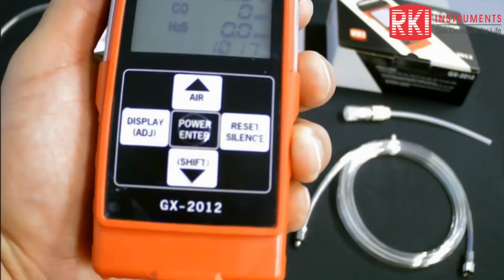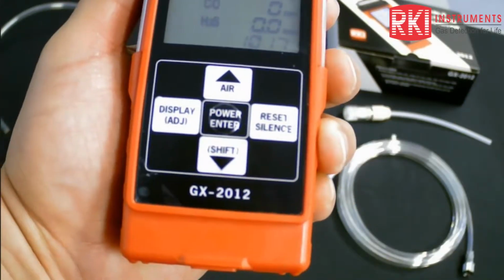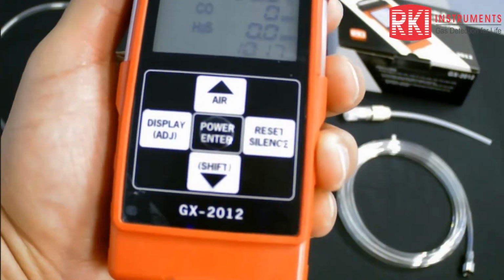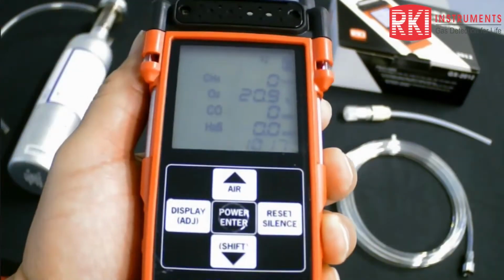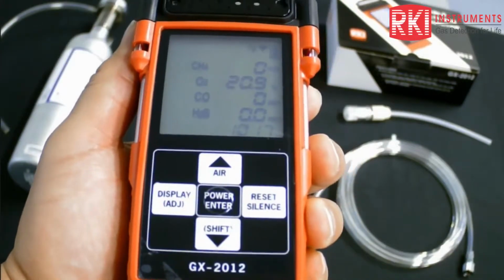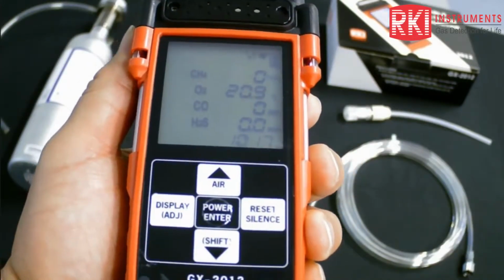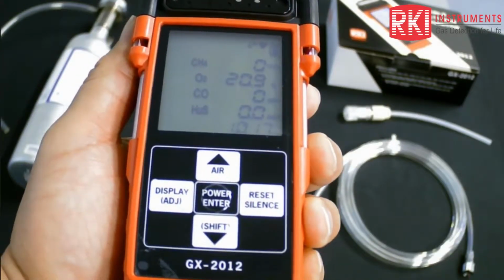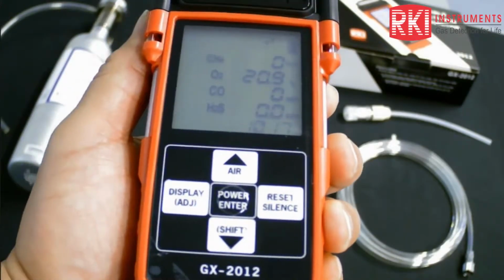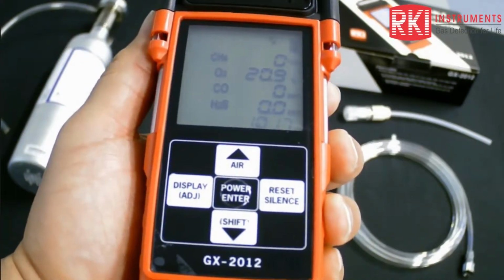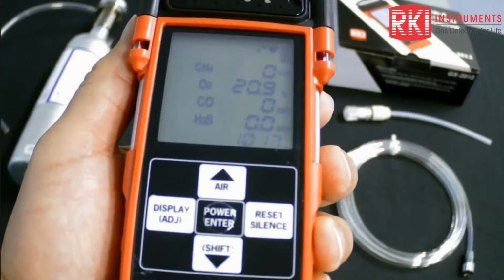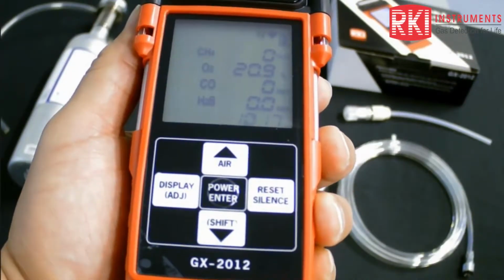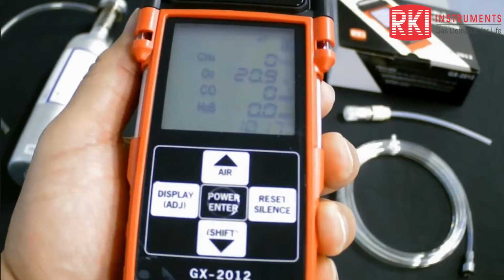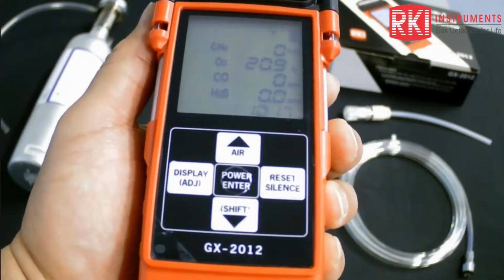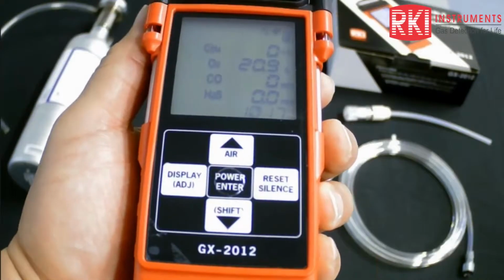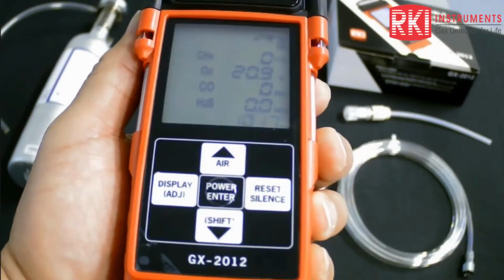Okay. In addition to those two sensors and technologies, we have what we call a galvanic sensor, or basically an electrochemical sensor, for the oxygen. That range is 0 to 40% by volume. Normal oxygen content at sea level is 20.9%. And then we also have, in this case, the CO sensor next, and the hydrogen sulfide sensors, which are electrochemical sensors as well. If you have combustion taking place, anything like that, then you would have need of a CO sensor. If there is no combustion taking place in your applications, then you probably don't need the CO sensor, as long as it's not a byproduct of whatever is going on in your application.